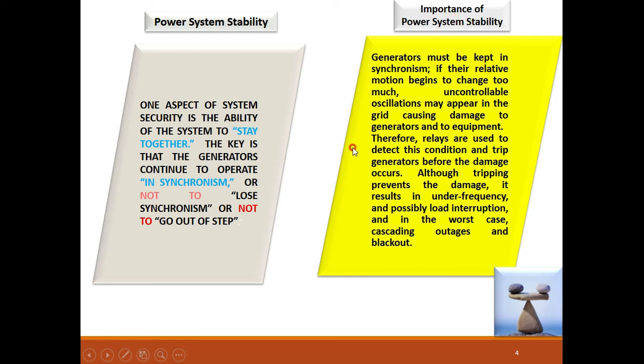The importance of power system stability is that generators must be kept in synchronism to make the system stable. If relative motion begins to change too much, uncontrollable oscillations may appear in the grid, causing damage to the generators. Oscillations come into picture when there is an imbalance — the load angle goes on changing and does not attain stable condition immediately. If the oscillations are too large, there is a possibility of losing synchronism. Relays are used to detect these conditions and trip generators before damage occurs.